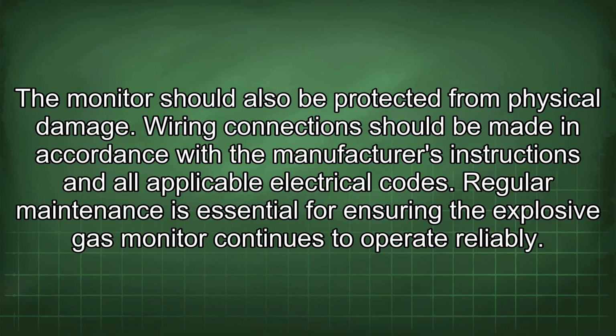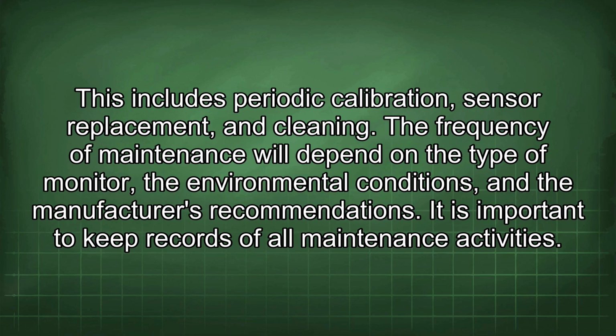Regular maintenance is essential for ensuring the explosive gas monitor continues to operate reliably. This includes periodic calibration, sensor replacement, and cleaning. The frequency of maintenance will depend on the type of monitor, the environmental conditions, and the manufacturer's recommendations. It is important to keep records of all maintenance activities.